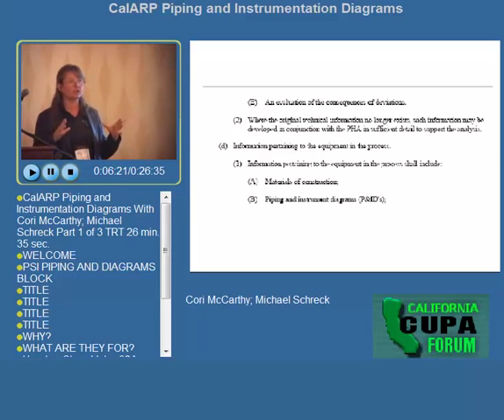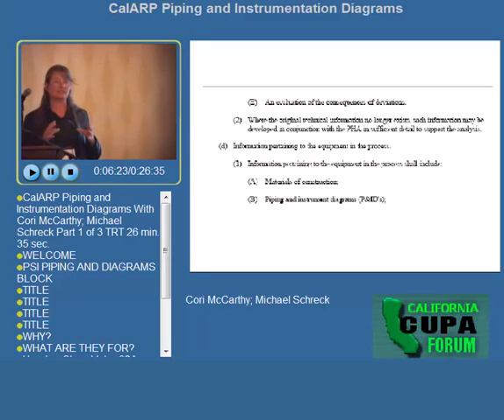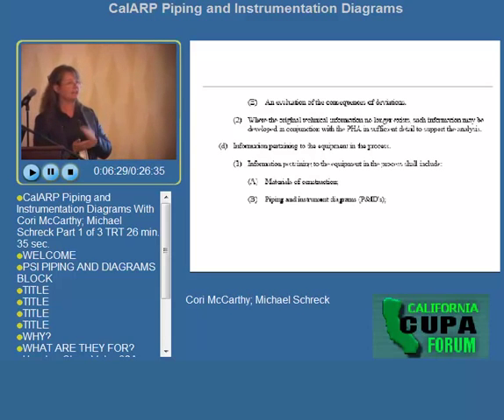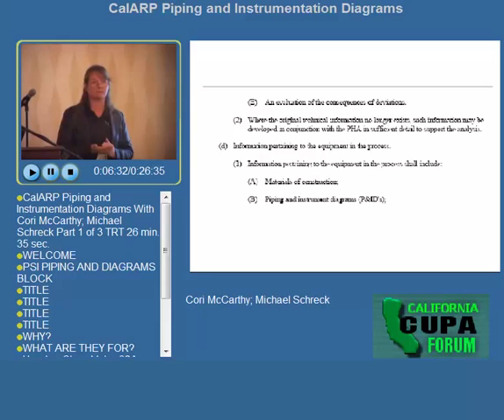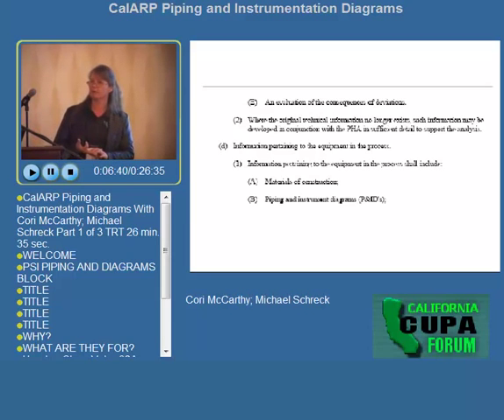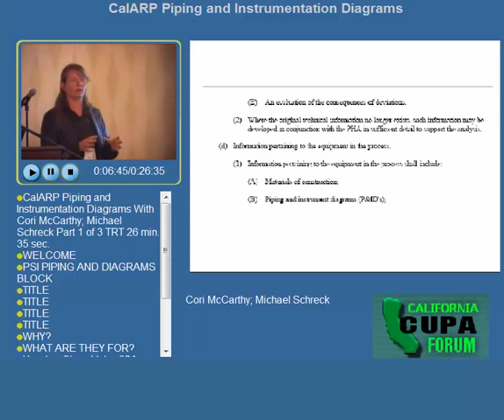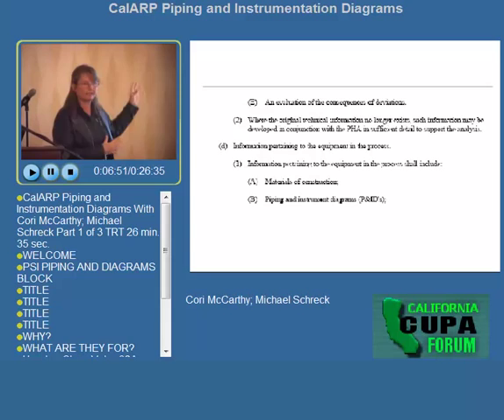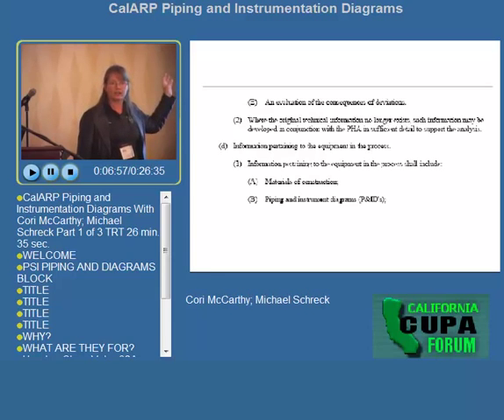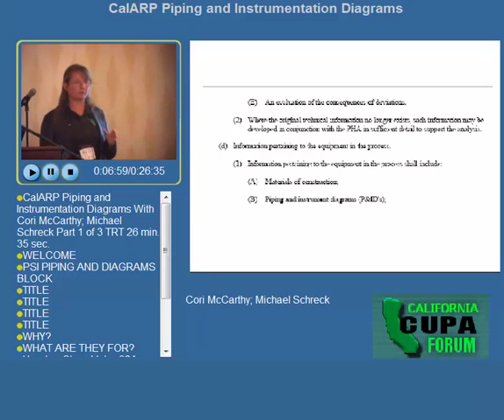Only a professional engineer with a specialty in refrigeration engineering can sign off. They can walk through a facility, inspect all the piping, and know that normal-temperature piping must be A53B ERW, smaller piping is A106, and low-temperature piping is A333. A refrigeration engineer can go through and certify that an entire plant was built to code and that the materials of construction are established for ammonia refrigeration processes.